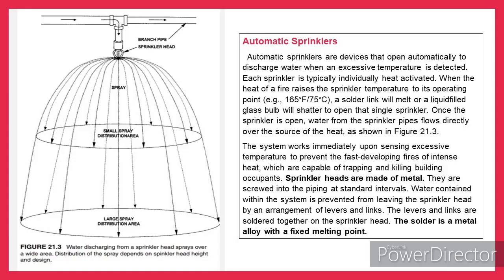of water. Automatic sprinklers are devices that open automatically to discharge water when an excessive temperature is detected. Each sprinkler is typically individually heat activated. When the heat of a fire raises the sprinkler temperature to its operating point, example 165° F/75° C, a solder link will melt or a liquid-filled glass bulb will shatter to open that single sprinkler. Once the sprinkler is open, water from the sprinkler pipes flows directly over the source of the heat, as shown in figure 21.3. The system works immediately upon sensing excessive temperature to prevent the fast-developing fires of intense heat, which are capable of trapping and killing building occupants.